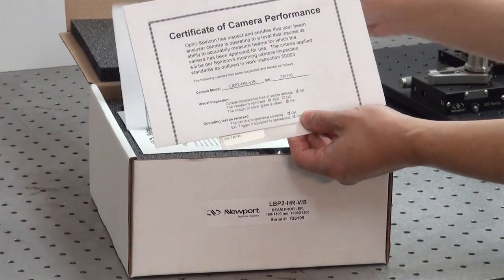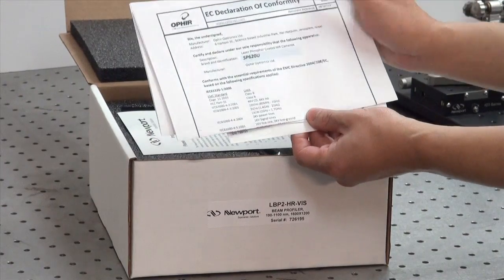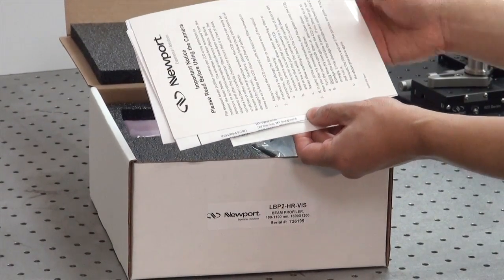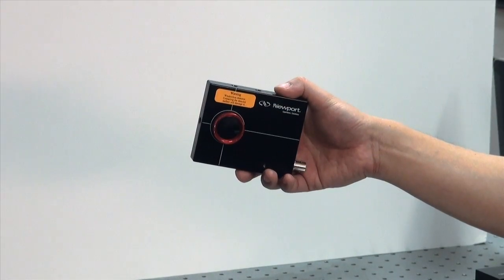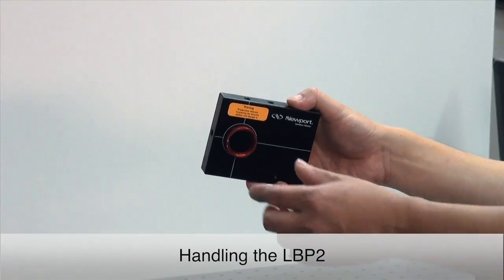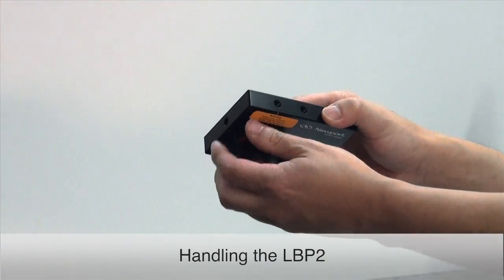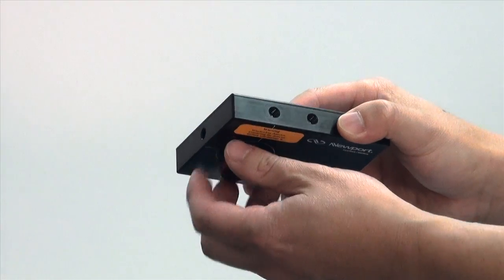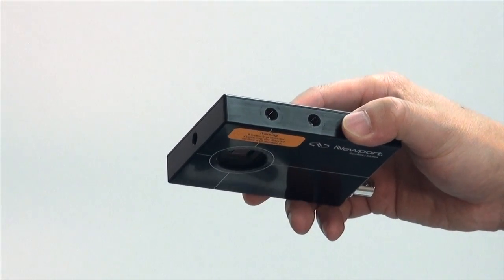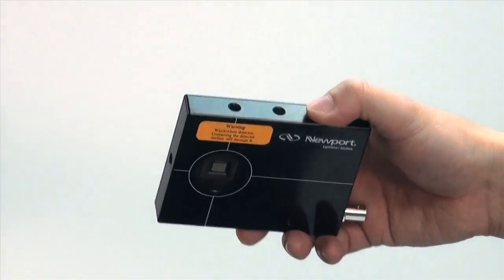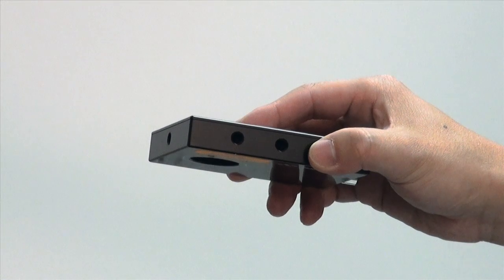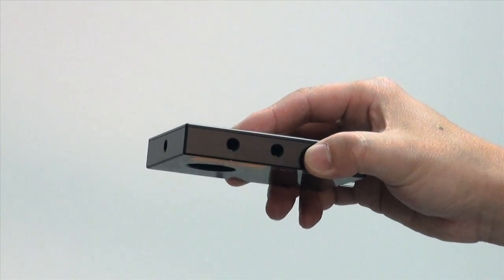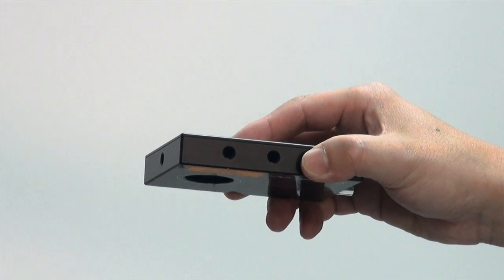When you first open the box, carefully review the contents. The camera requires special attention. The sensor is directly exposed to air to minimize the unwanted interference pattern when viewing the laser beam profiles. Make sure that either the protection cap or filter is always mounted on the CCD.